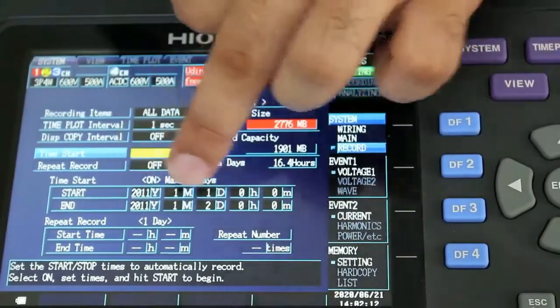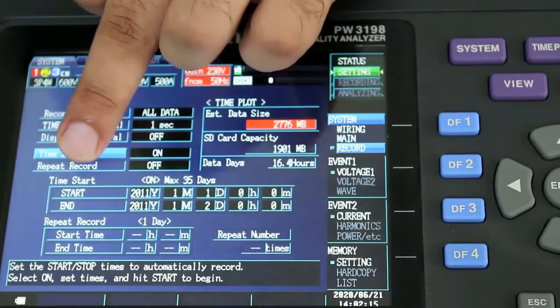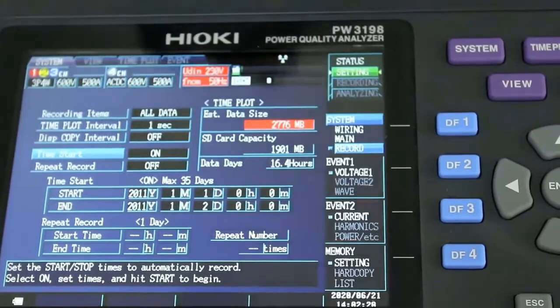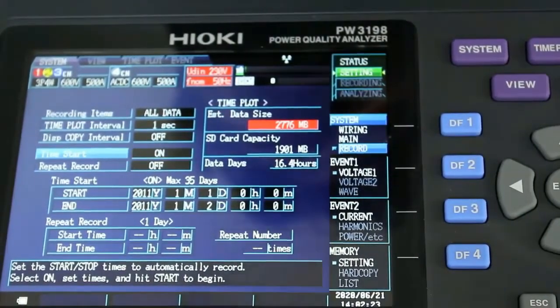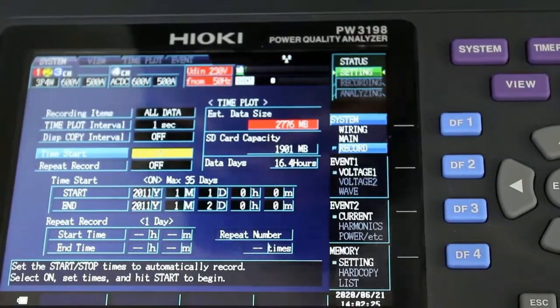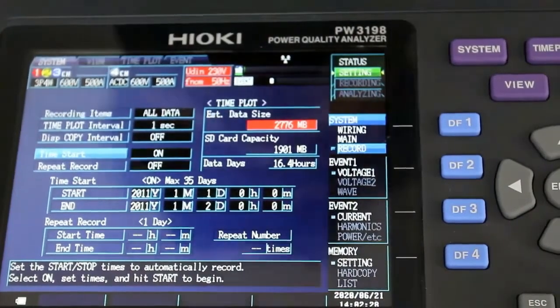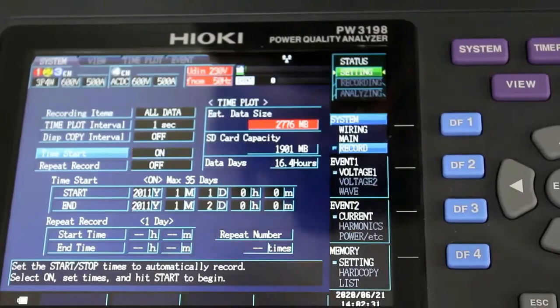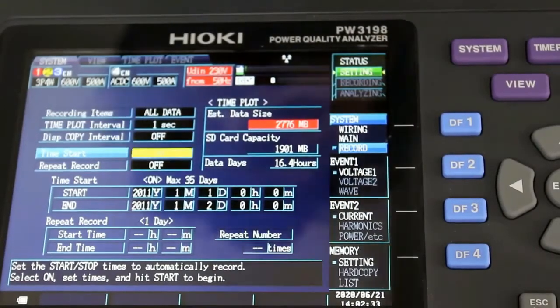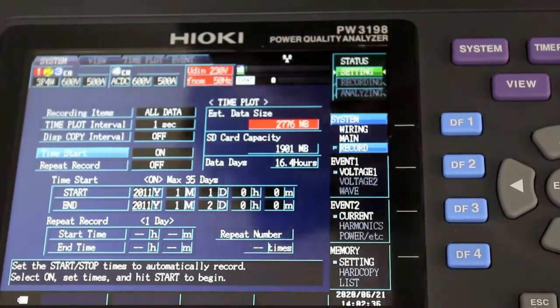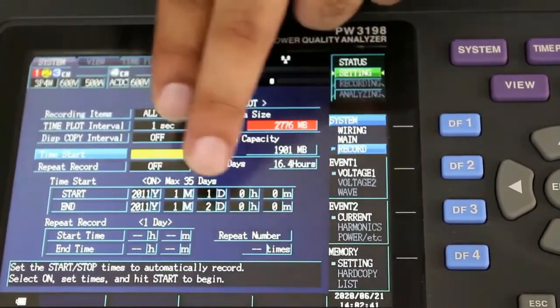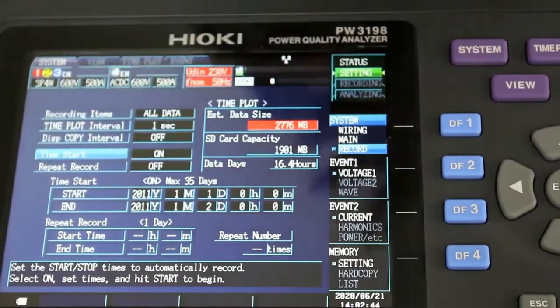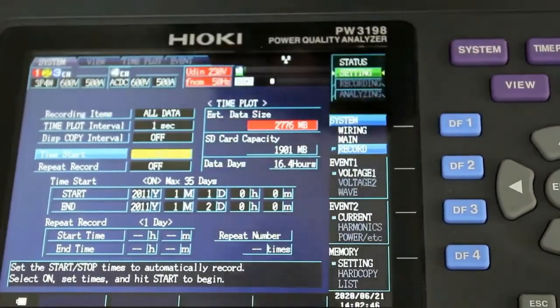Now I'll switch it on, and you can see this is activated. We can select the start time and end time as per requirement. For example, if I want to log data at night from 12 AM to 3 AM, I don't need to be there. I just switch on the instrument, do all the settings, and set the start and stop recording time and date. It will automatically record and stop, and next morning I can collect and analyze the data.